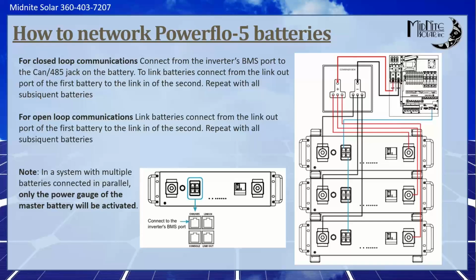Question: what if we use bus bars to connect the 4? So they're asking if they could run a copper bus bar across. You certainly could, or if it was in a cabinet like an EG4 cabinet, yeah you could do that. That's totally up to you, and then you could run one set of large cables. If you're going to daisy chain a stack of batteries, I do recommend pulling across corners or out of the middle. In a stack you could pull across the corners or pull off the middle battery to go up. Just keep in mind, don't pull off the same battery every time. If you've got 8 stacked up, don't pull off just the top battery, because the bottom one will lag way behind.